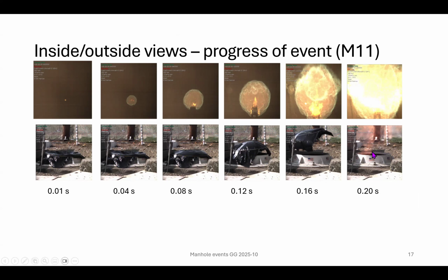At that time the cover starts lifting. In the first hundredths of a second, the pressure starts building up for about 0.12 to 0.16 seconds. Finally the sphere of ignited gases reaches the cover, and that's when the cover starts feeling it and starts lifting.